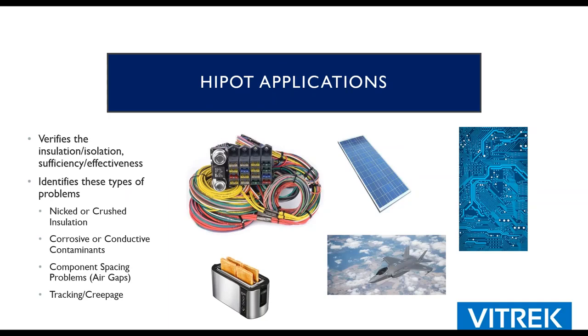So applications, there are any number of applications. It's really limitless. And our testers don't really know the difference whether you're connected to a toaster or a printed circuit board or a billion-dollar airplane. At the end of the day, the measurement is always going to be the same. You're going to have two conductors separated by an insulator. We want to verify that there's near zero current flow, or that the amount of current flowing between those two conductors is not more than what would be expected.